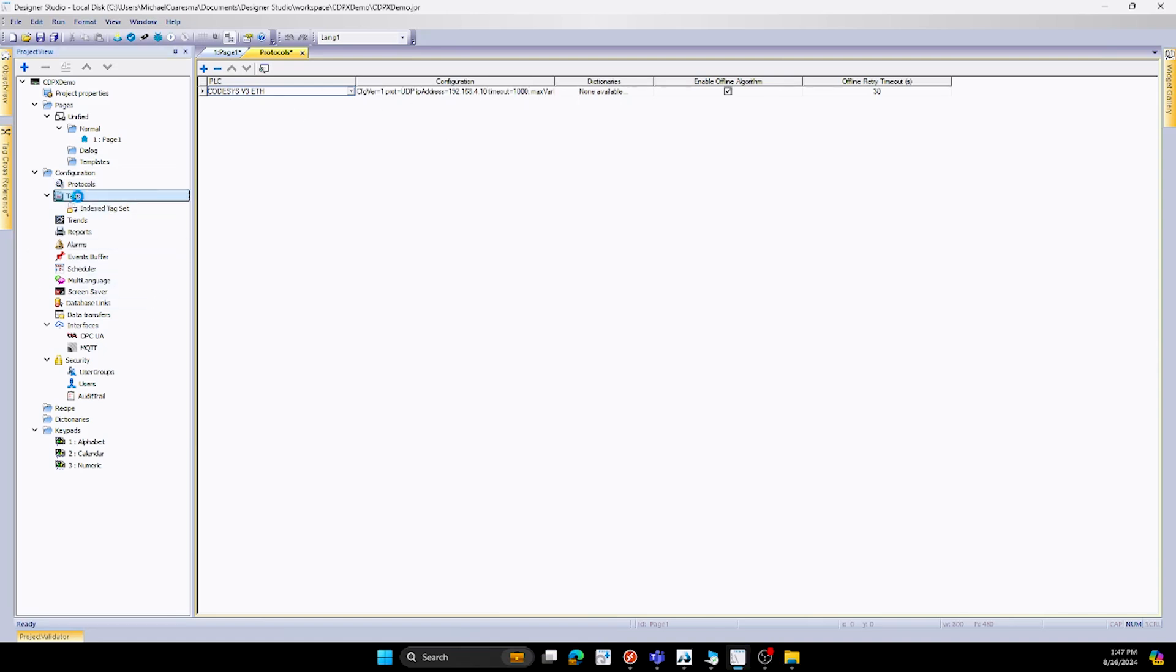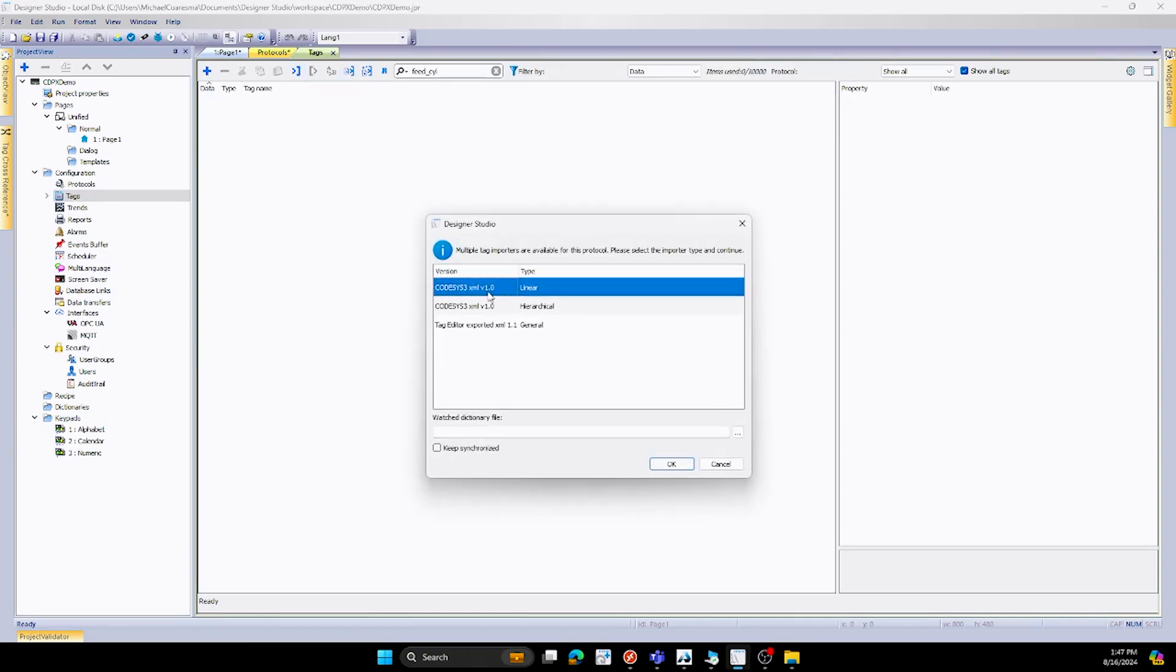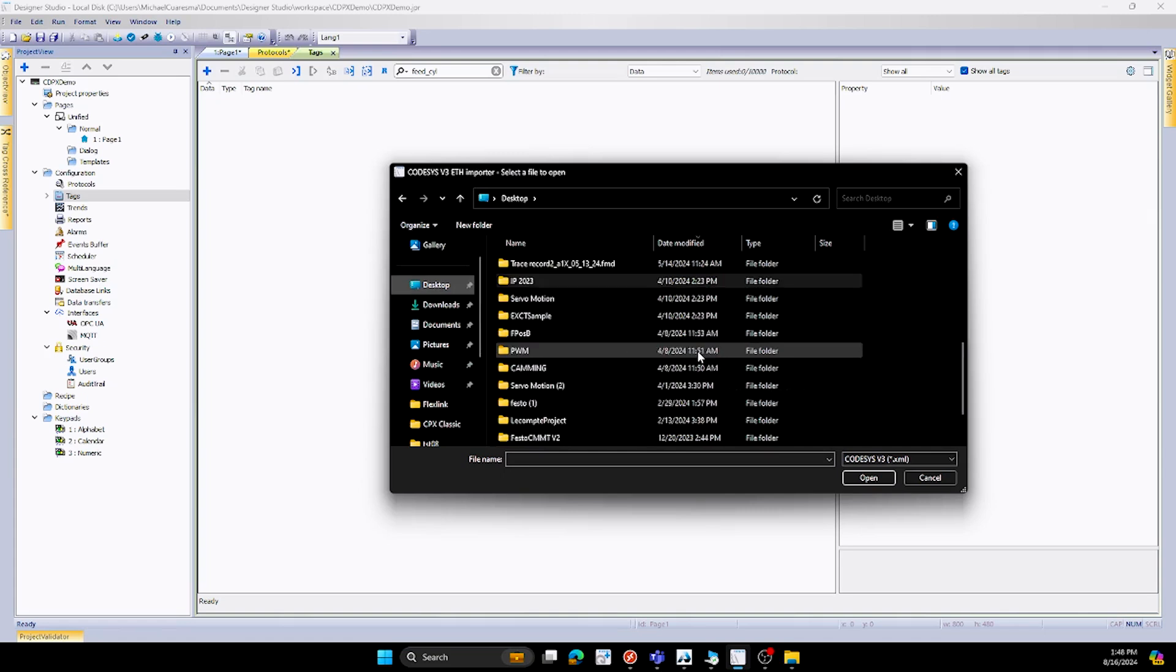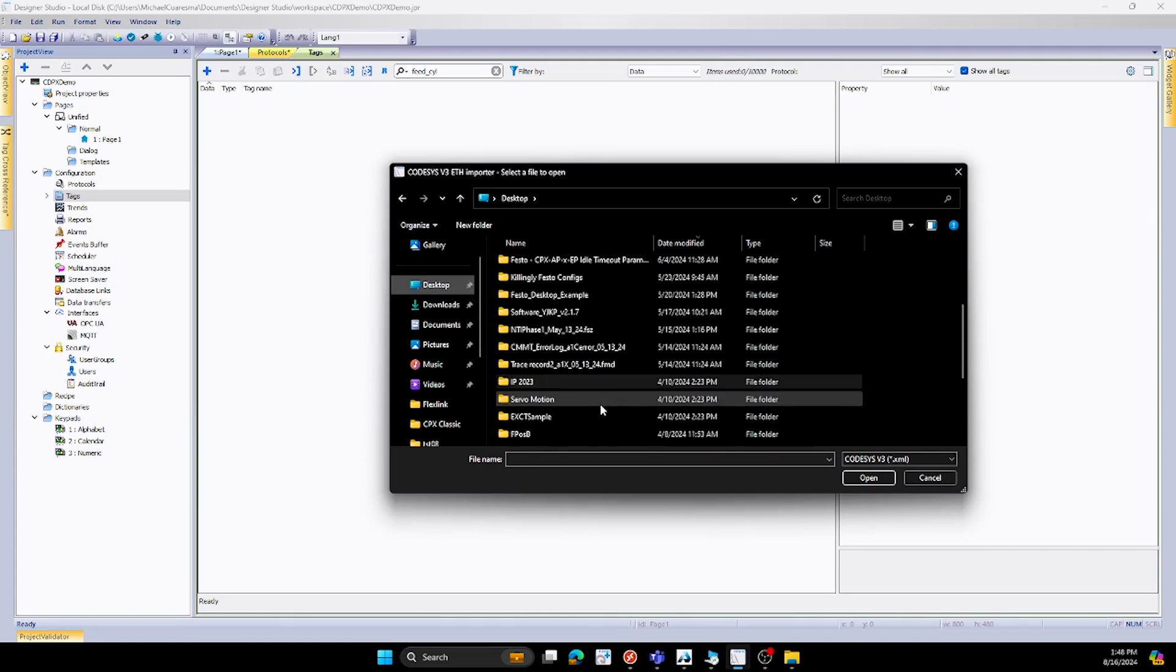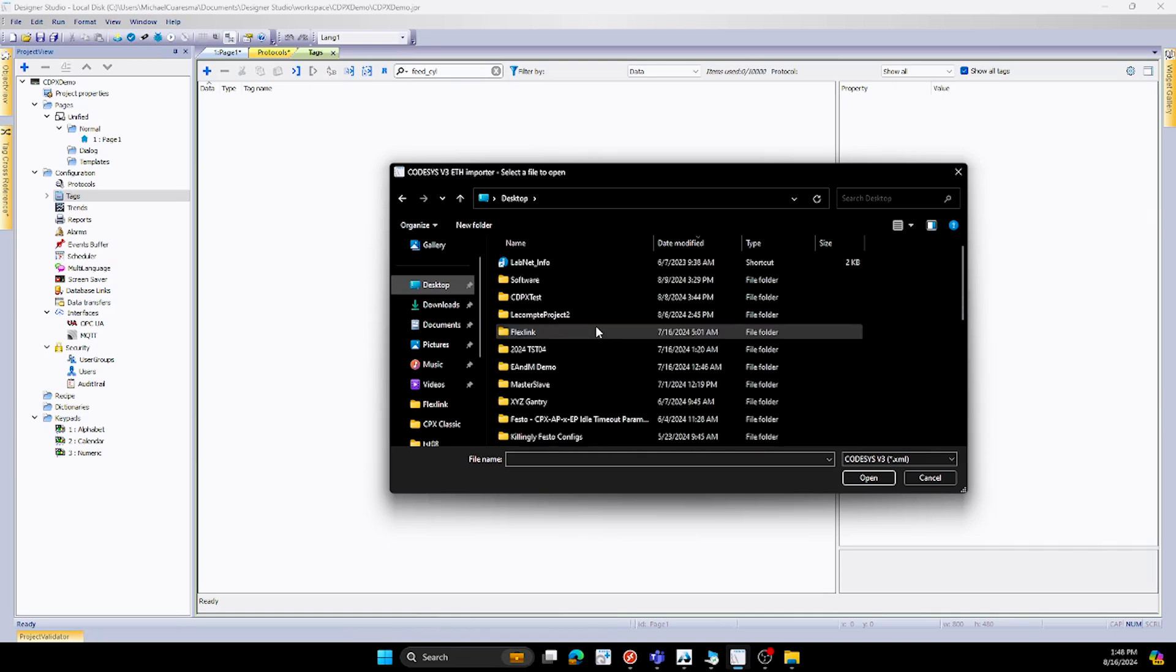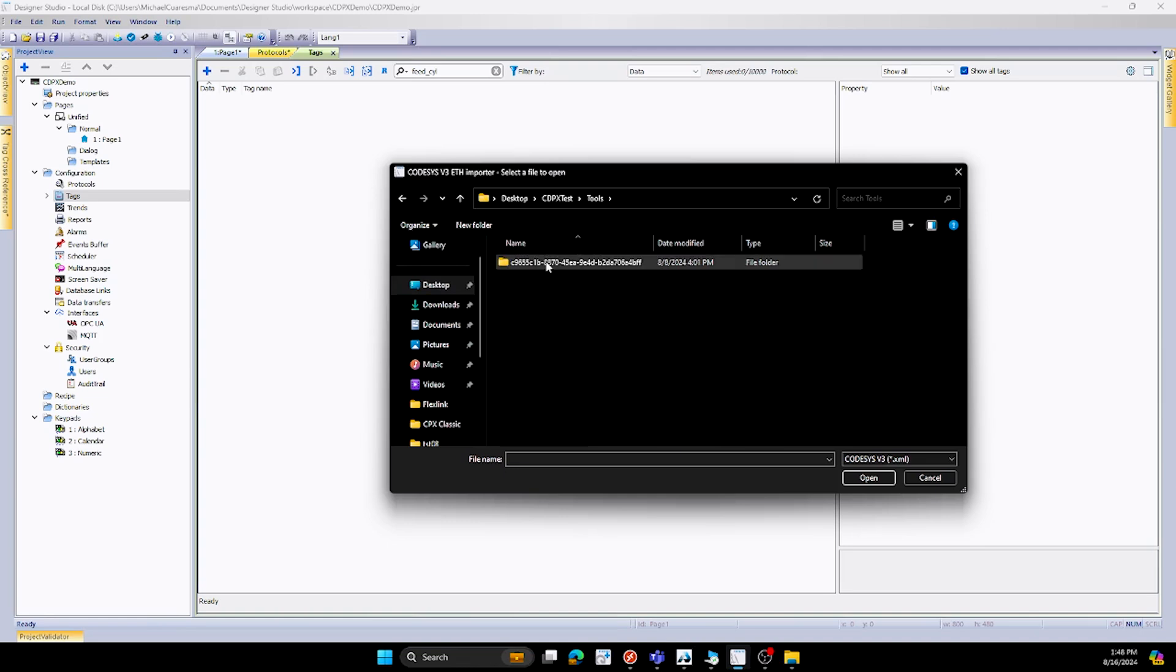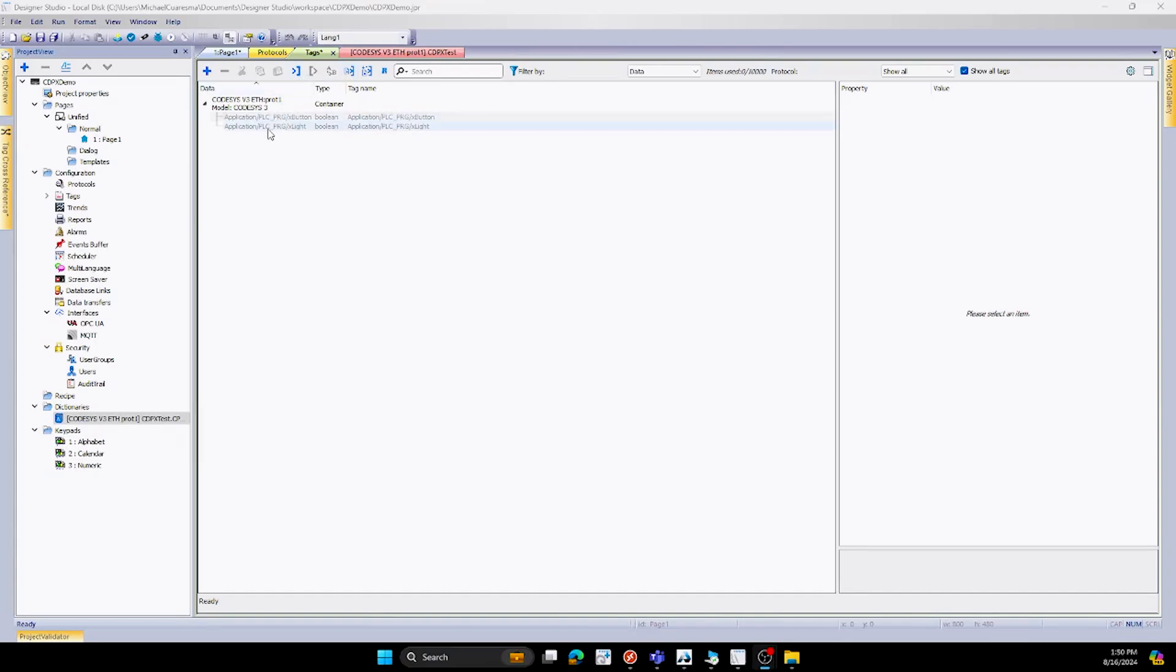Now we can go into our tag section. Once we are in our tag section, we can go to import dictionary right here. We'll want to go with linear. We want to hit OK, and we want to find the project that we are working on. So for me, I'll go to my desktop, and it would be under CDPX demo. PXTest right here. Double click on that. You'll want to go into Tools. Double click this one, and you'll notice that this is the XML file that I created. Once I hit Open, it'll have a little pop-up window that says two tags added, and I hit OK.